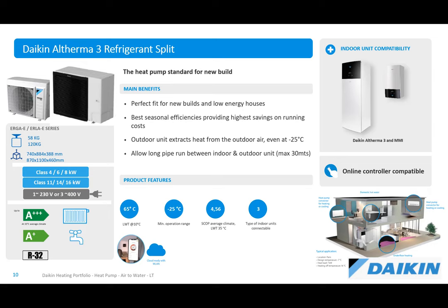They give you a higher efficiency over a monoblock, generally speaking. And they also allow you to have a longer distance between the indoor and the outdoor unit. So it allows you to have about 30 meters of a pipe run between the indoor and the outdoor, whereas with the monoblock, you're really restricted to about 10 to 12 meters. So that's the refrigerant split.